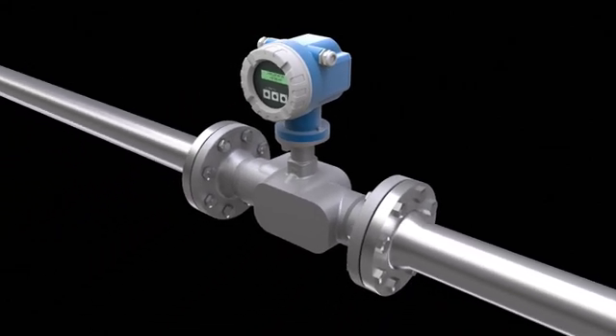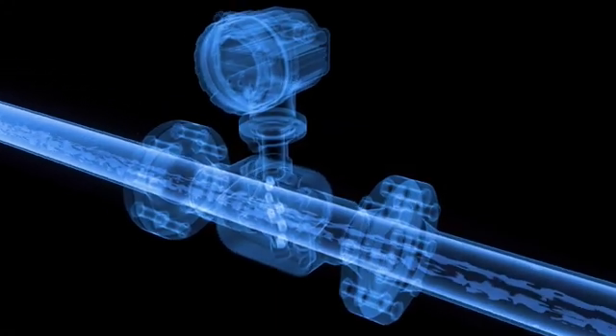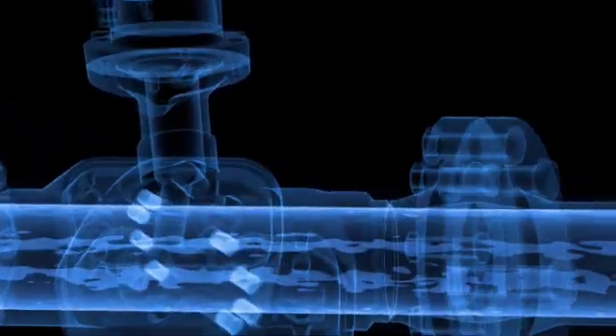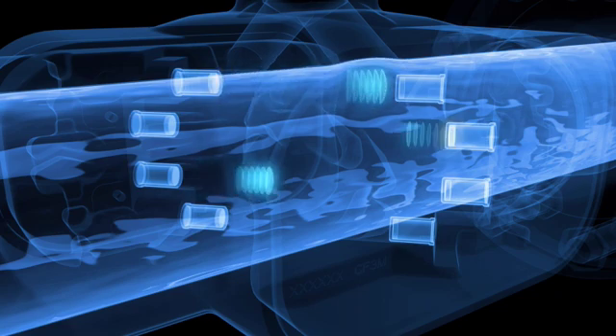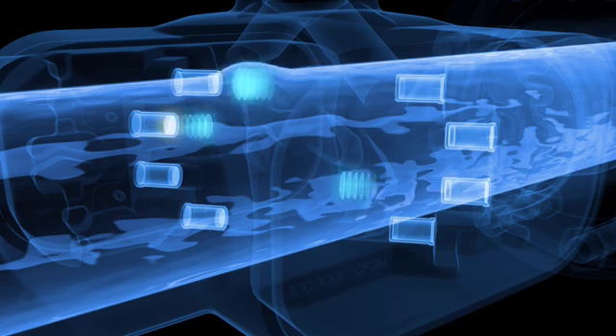Here is how this measurement method works. Inside the ultrasonic flow meter, pairs of sensors are fitted across from each other in the measuring tube. Each sensor can alternately transmit and receive an ultrasonic signal. Simultaneously, the transit times of these signals are measured.